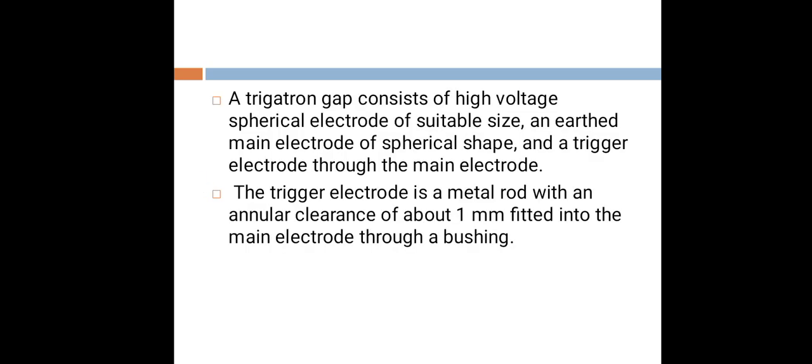This is the structure of the impulse generator. A trigatron gap consists of a high voltage spherical electrode of suitable size and an earthed main electrode of spherical shape, and a trigger electrode through the main electrode. The trigger electrode is a metal rod with an annular clearance of about 1 mm fitted into the main electrode through a bushing.